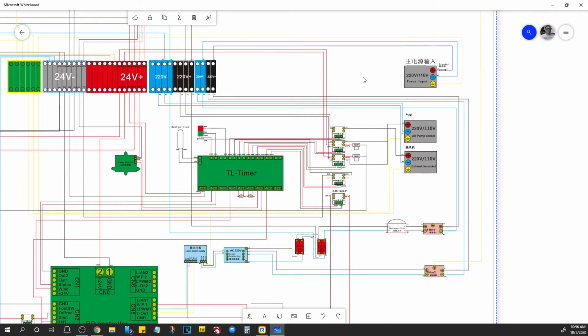So here's how it works. Once your power goes in, it goes through to the terminal block through the breaker, and then it's all distributed from here, from this section. Now we're dealing with 110. This is a Chinese document. It says 220 here, but just know that this is 110 for all the USA versions. So the main power is distributed through here. They go through some filters. There's filter 1, filter 2.